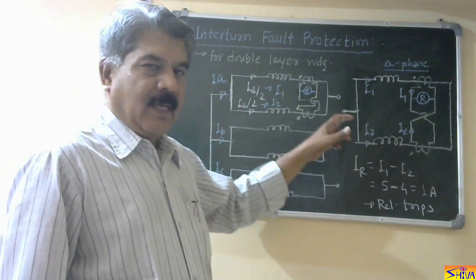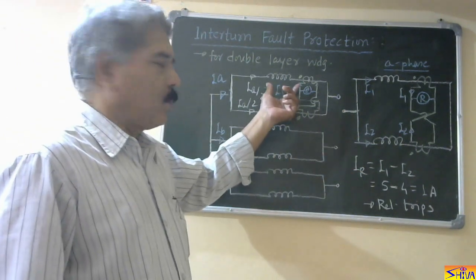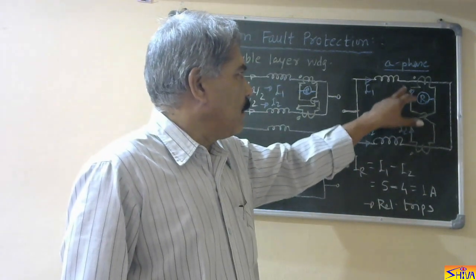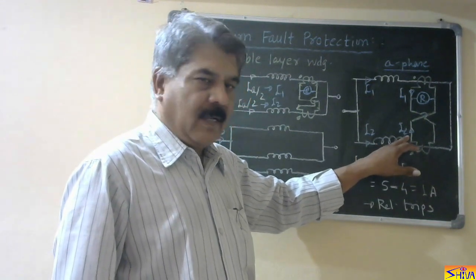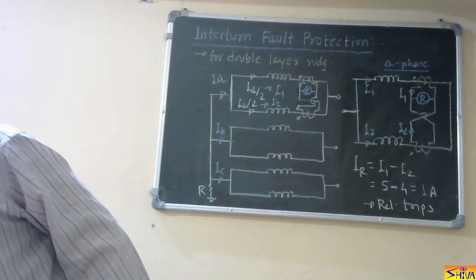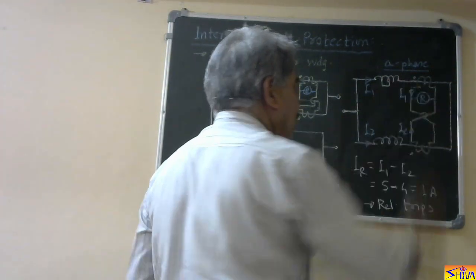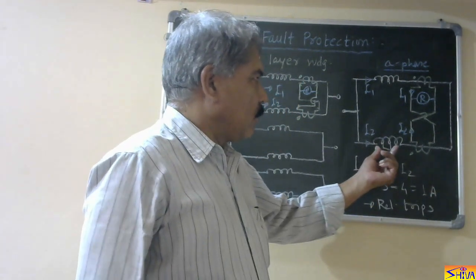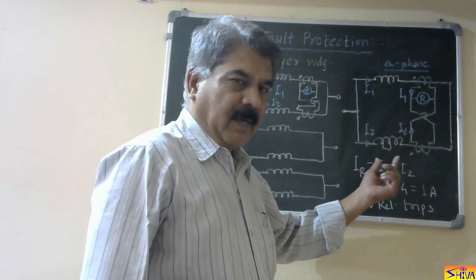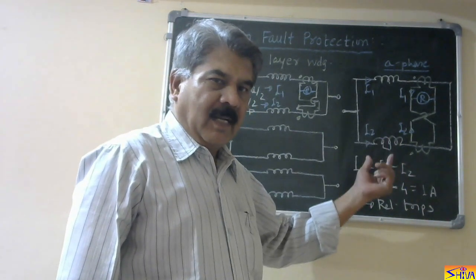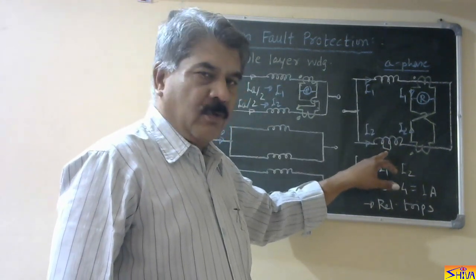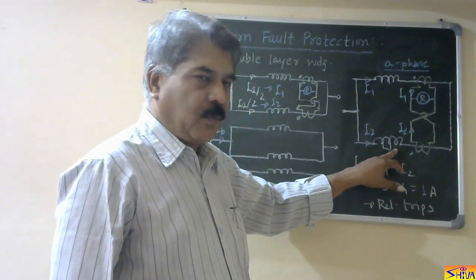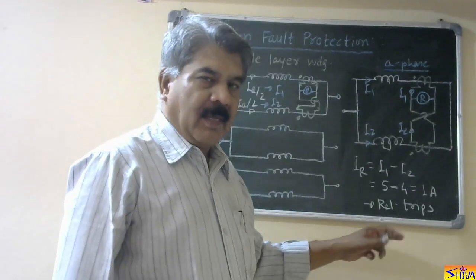Let us say 1000 amperes is the current in phase A. Under normal conditions, 500 amperes flows through each winding layer. Using a CT of 500/5 ratio, each CT secondary produces 5 amperes, so the net relay current is zero. Now suppose there is an internal fault where some portion of one winding layer is bypassed. This current remains 500 amperes in the healthy layer, but due to reduced EMF, this current becomes 400 amperes in the faulted layer. So I1 is 5 amperes and I2 is 4 amperes — the net current through the relay is 1 ampere, and the relay trips.